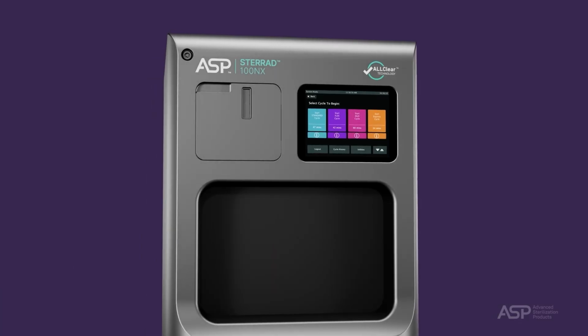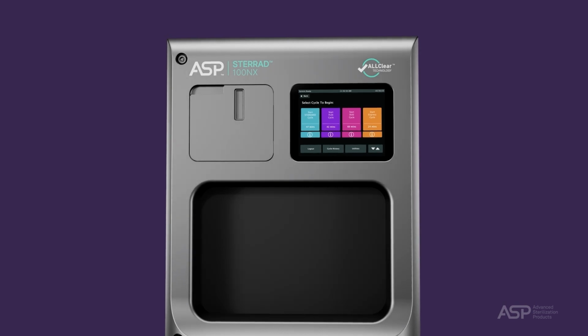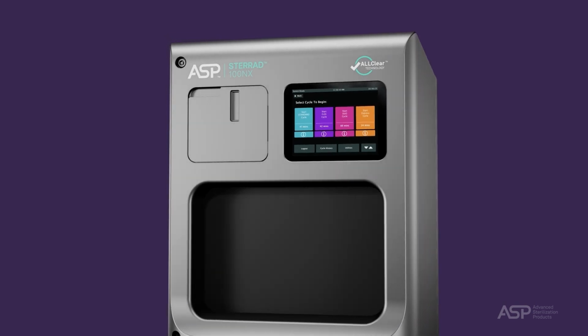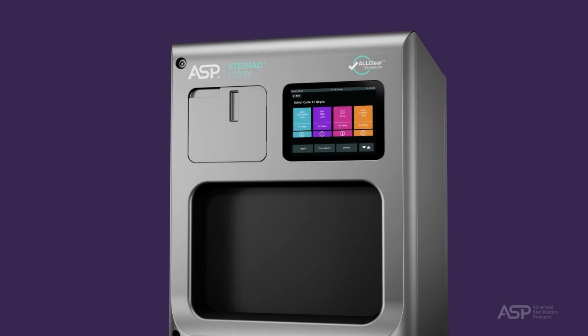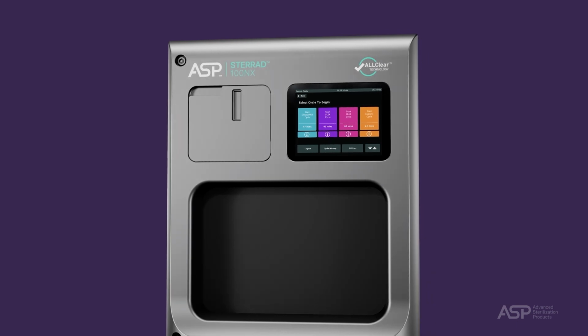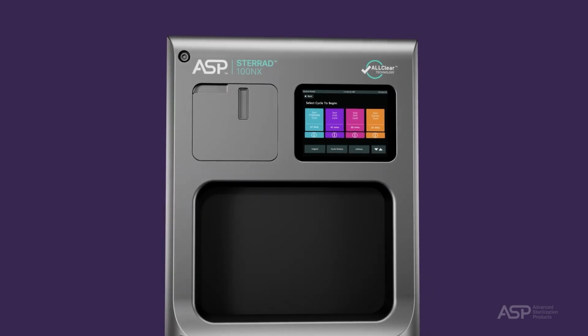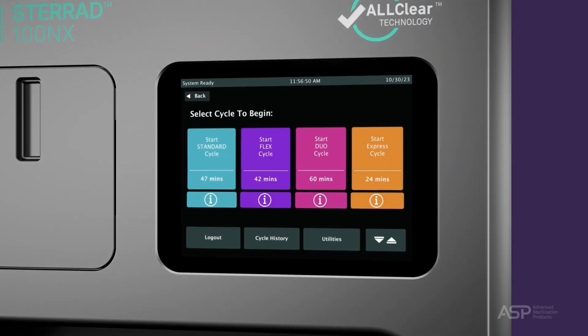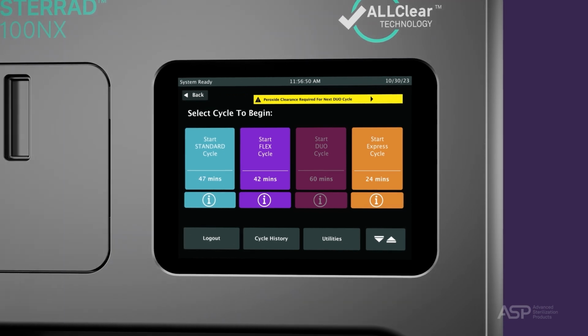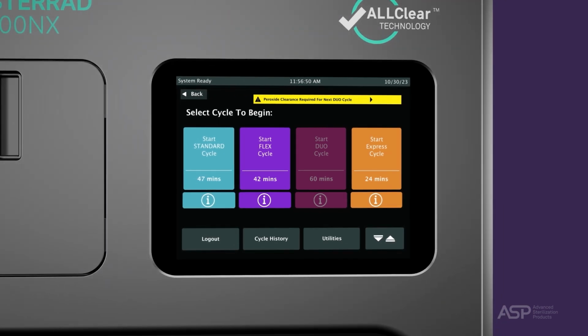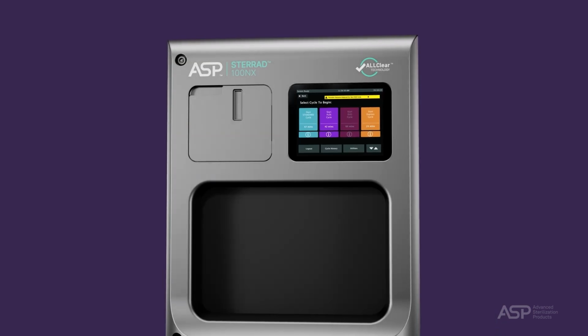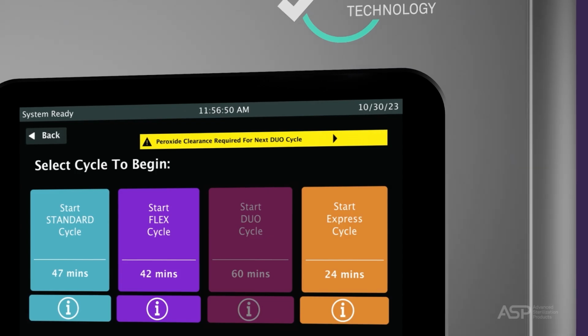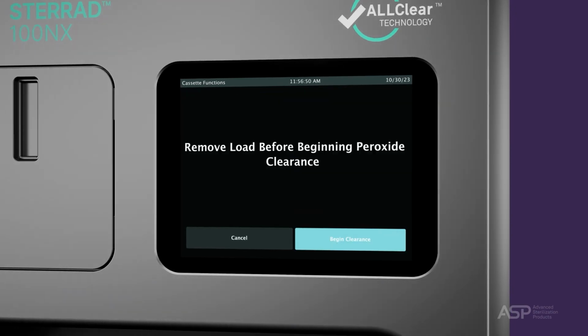The Duo cycle requires the sterilizer to hold peroxide in a reservoir to optimize sterilization. If this peroxide expires, you must dispose of the peroxide remaining in the system. Peroxide clearance must be performed when a message appears. Otherwise, no subsequent Duo cycles can be run.